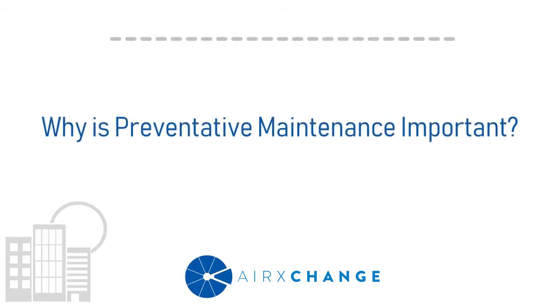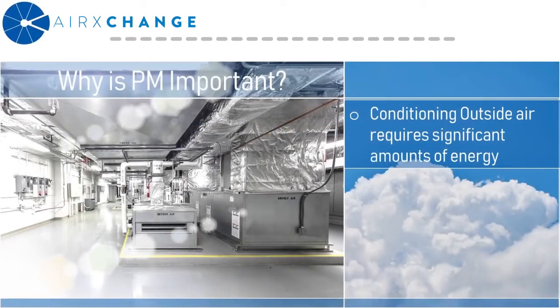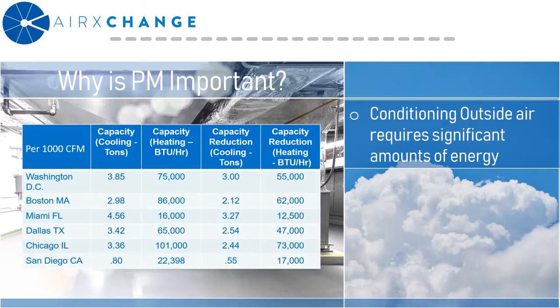So why is preventative maintenance of energy recovery devices important? Well, first and foremost, it takes a significant amount of energy to condition outside air. Looking at some localized energy models for representative cities, as you increase the amount of outside air, it's going to have a major impact on how much energy is required to condition that air.